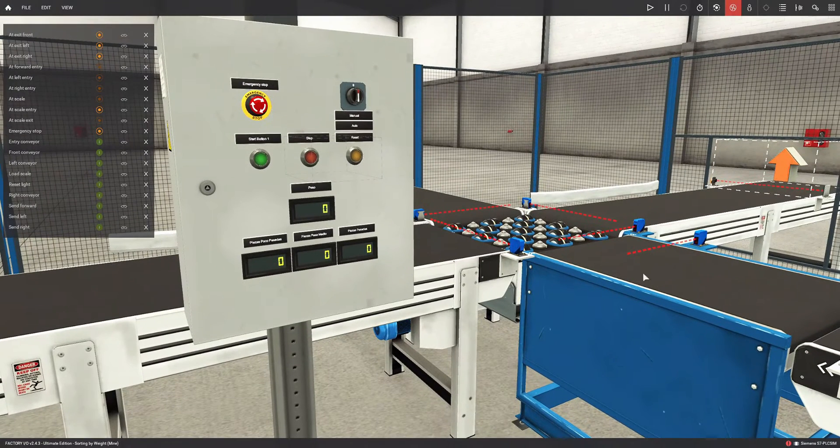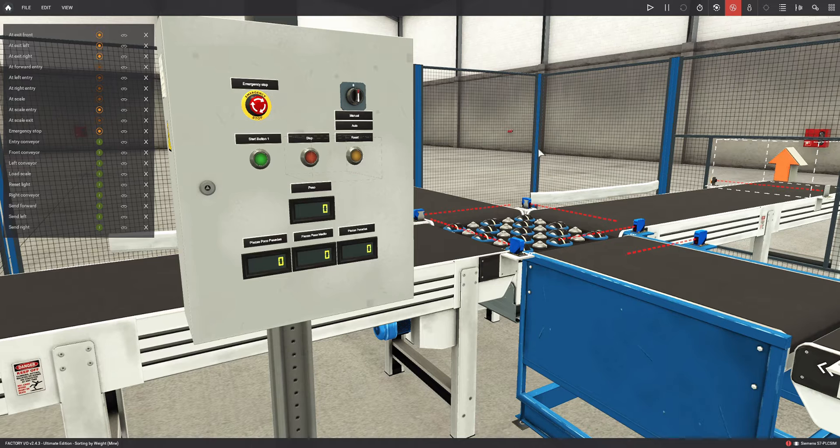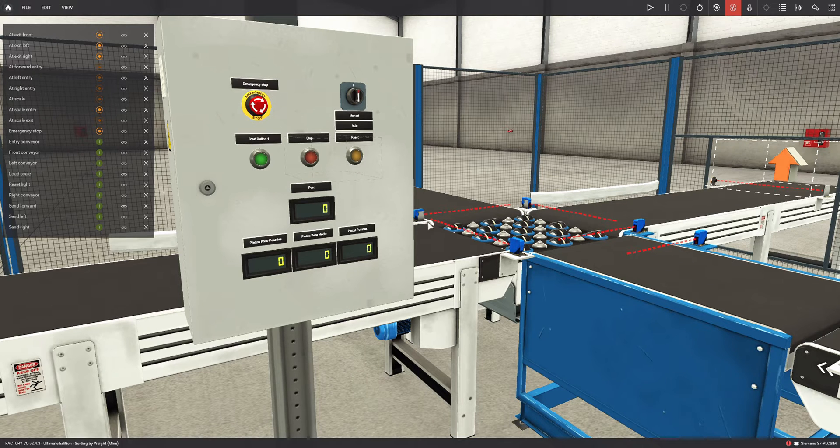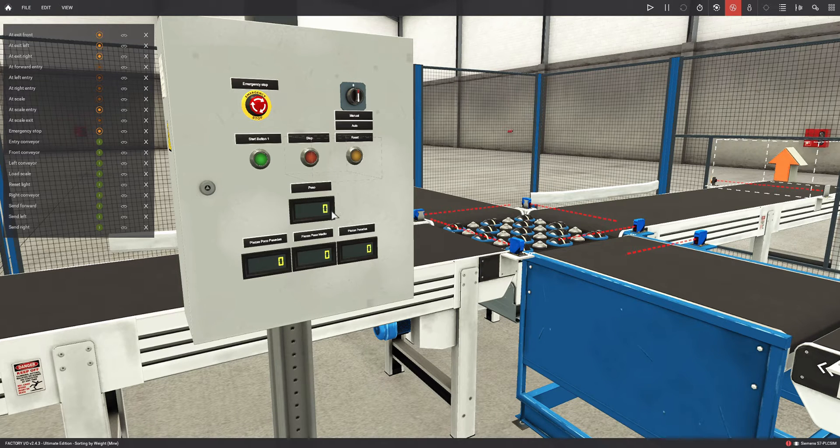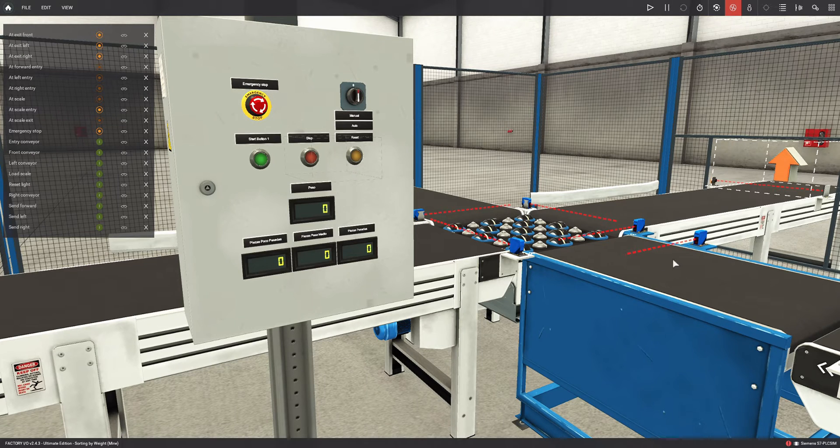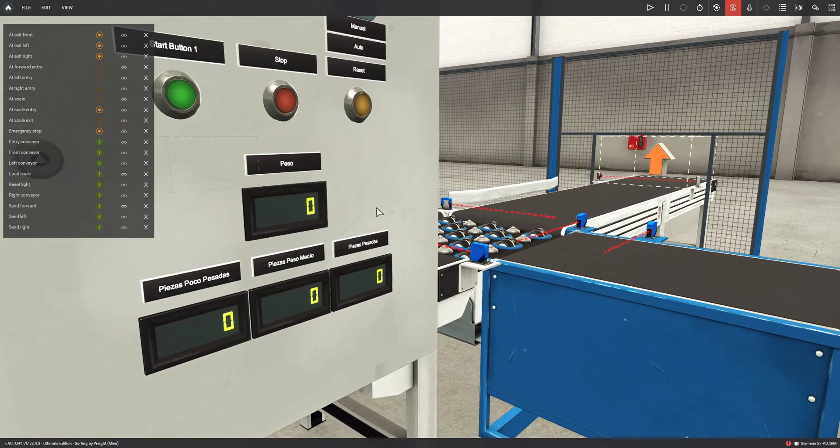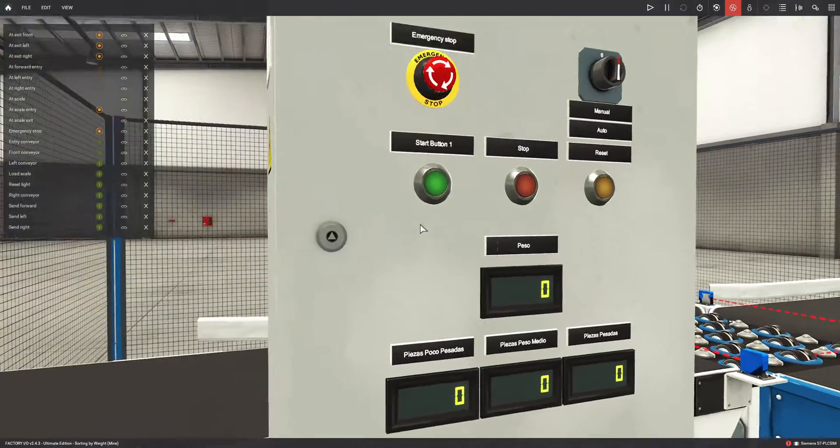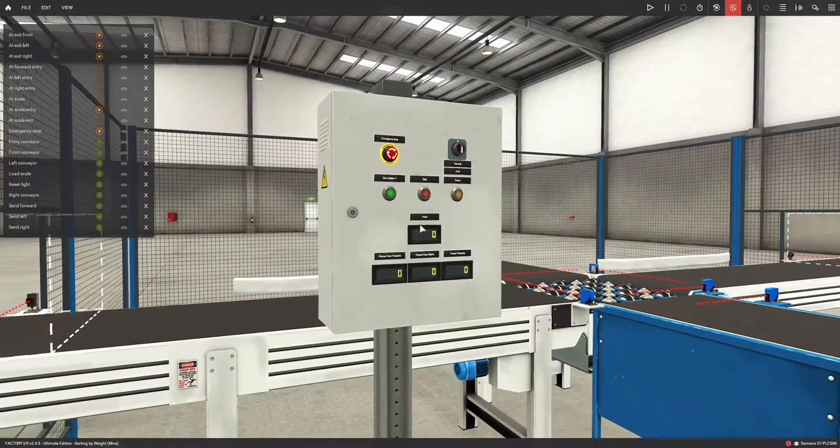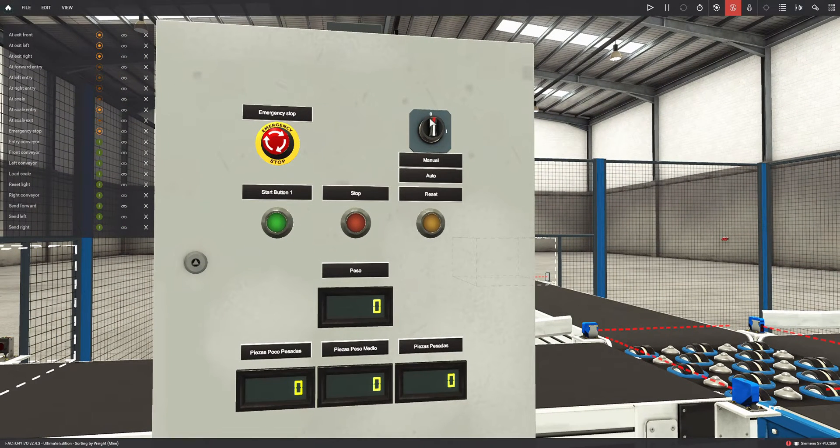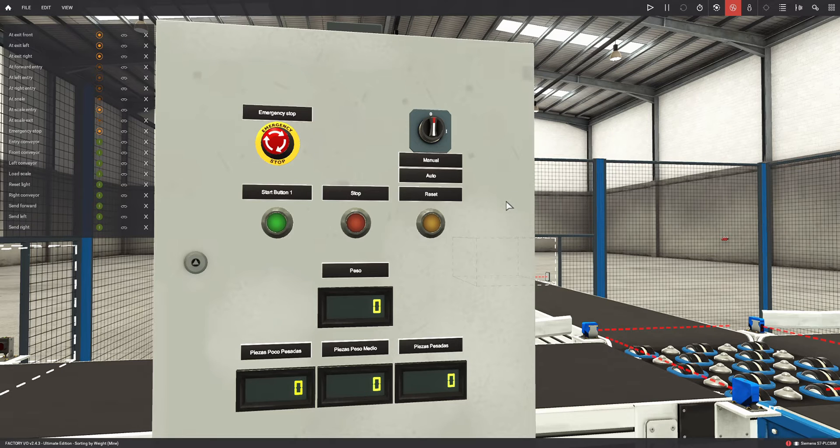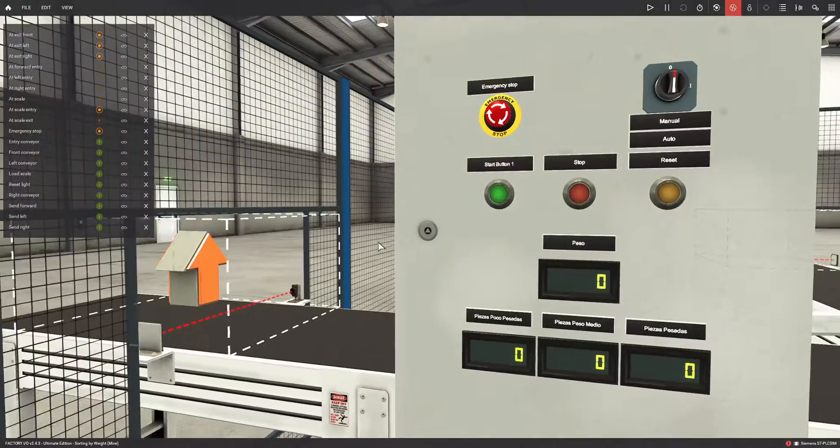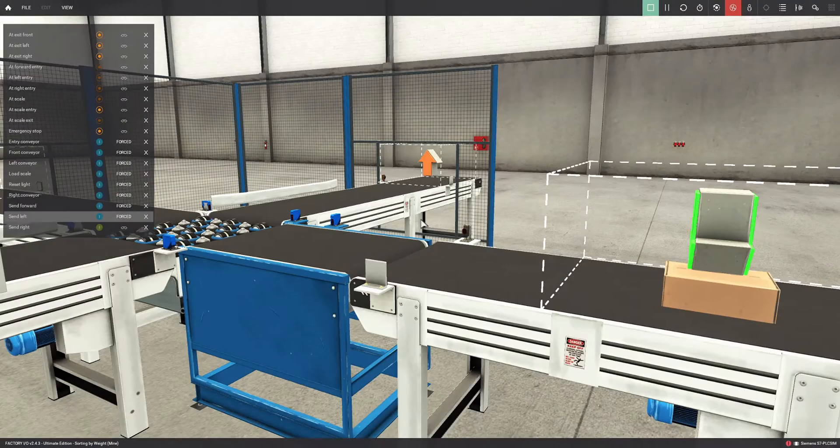It's worth noting that these are very sensitive objects. The conveyor is very sensitive, and when an object is moving on it, the weight will vary and won't stay at an exact value. So what should be done in the programming is that the value this display captures, this weight, should be when the conveyor is stopped. That's why this photocell is in this location, so that once the piece is here it can be weighed and classified accordingly. I haven't considered this manual and automatic mode selector for the programming because this is just an example. Now we can begin with the explanation.